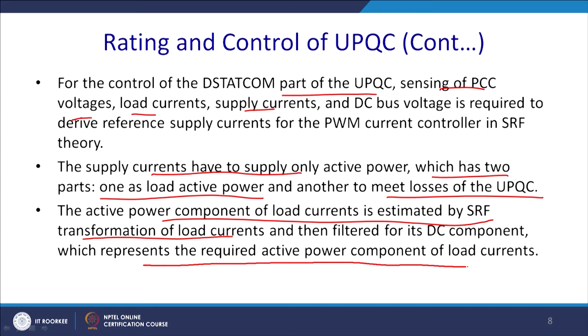The supply current has to supply only the active power, so that the source always sees it as if a resistive load is connected to it, irrespective of the pattern of the load. This has two parts: one is the load active power, and another is to meet the losses of the UPQC. These are the two parts you have to fit. Losses of the UPQC have to be met by real power. The active power component of the load current is estimated by SRF transformation of the load current, and then filtering its DC component. We shall see the block diagram of it, which represents the required active power component of the load current. We are describing it first, thereafter we shall show how it is done by a block diagram.